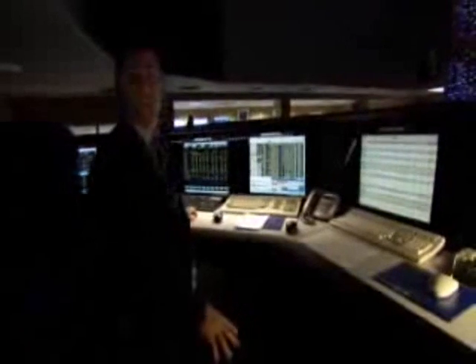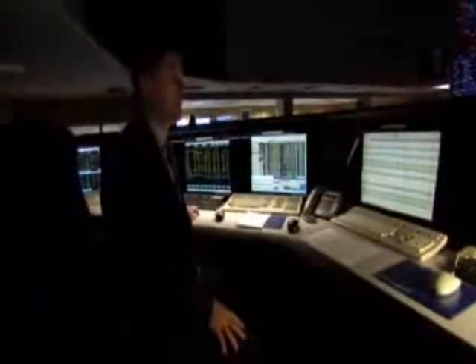Power surges like this are unique to Britain — no other country in the world switches on so many kettles in so short a time. To cope with the strain, Simon has had to put specialised power stations on standby as far away as Snowdonia and Scotland. These hydroelectric plants can set thousands of tons of water plunging down the hillside at a moment's notice, generating huge bursts of power in a matter of seconds. Simon is also asking neighbours across the channel for a favour: the French link is picking up 600 megawatts at 100 megawatts a minute — again, a very rapid response.